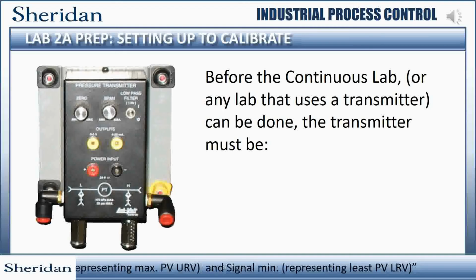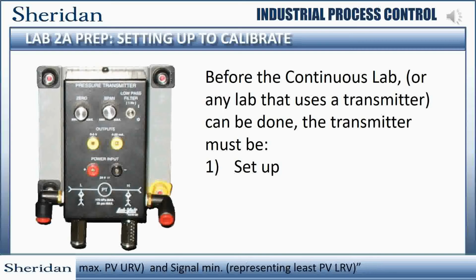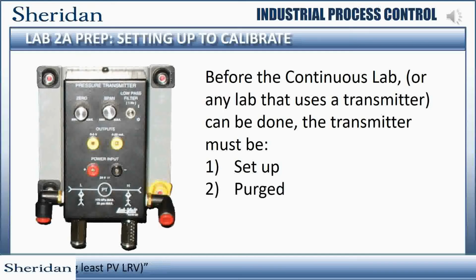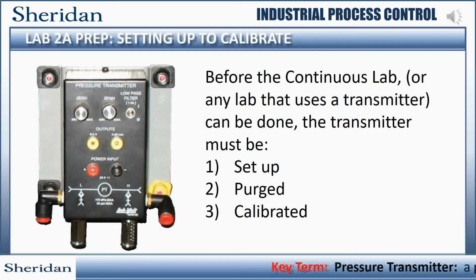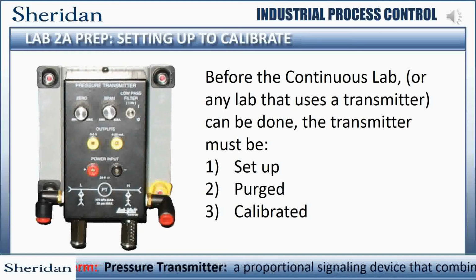The basic three steps are: 1. Setting up the equipment, which includes the proper location and mounting of the device, making the signal connections, and connecting the fluids involved. The second step is to purge or blow down the transmitter of any unwanted fluid or debris that may have entered the device. The third step is, once purged, the transmitter must be calibrated in situ, or where it's going to be used, since the hydrostatic pressure is directly related to the elevation of the device relative to the process fluids involved.